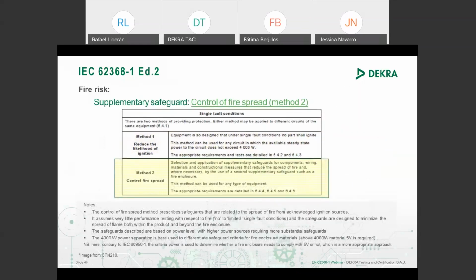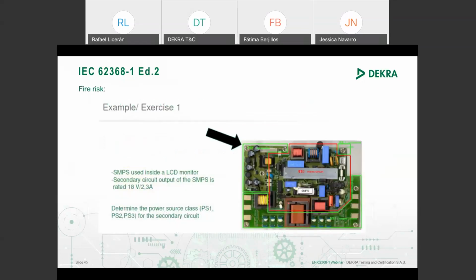Method 2 is the control fire spread method, and is the method which requires a fire enclosure. Okay, we contain the fire inside of my device and it does not spread to the outside. This is the useful method to use.